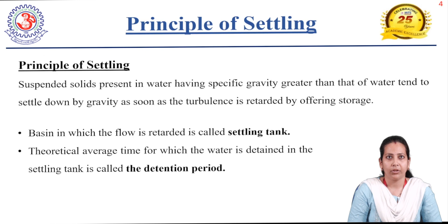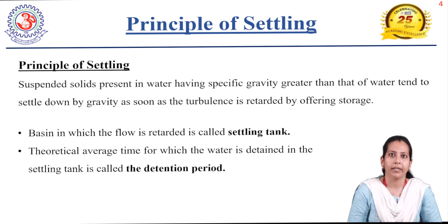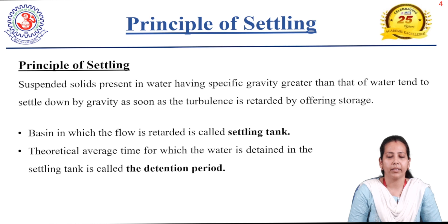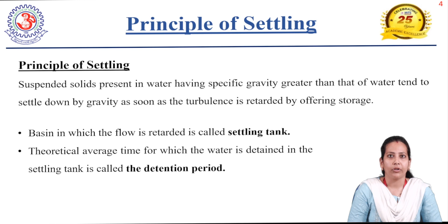The basic principle of settling is that suspended particles or impurities in suspension tend to settle down at the bottom of the tank, because those particles have a specific gravity greater than water, and they settle by gravity as soon as turbulence is retarded. The tank in which flow is retarded is called the settling tank. The theoretical average time for which water is detained in the settling tank is called the detention period.